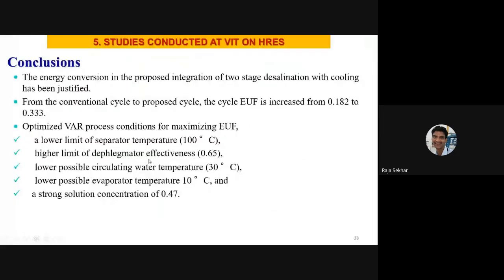So regarding the effectiveness of this dephlegmator, don't think it is something sophisticated - it is also a kind of heat exchanger only. We were able to increase that heat exchanger effectiveness to around 0.65, and achieve the lowest possible circulating water temperature at 30 degrees, with the evaporator temperature at 10 degrees. This is very important: a strong solution concentration of 0.47 is obtained. If you look into the literature, nobody has attained a concentration of this level.